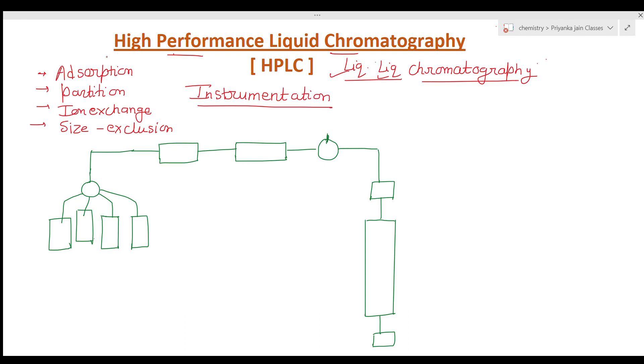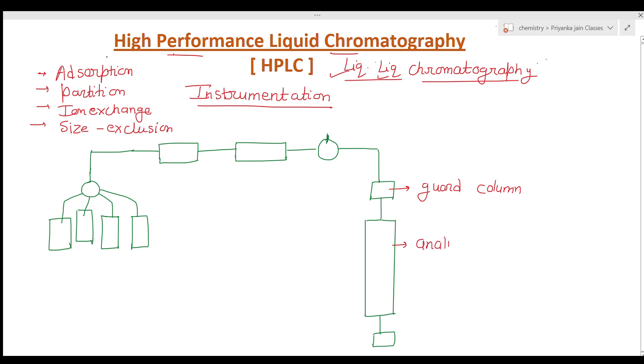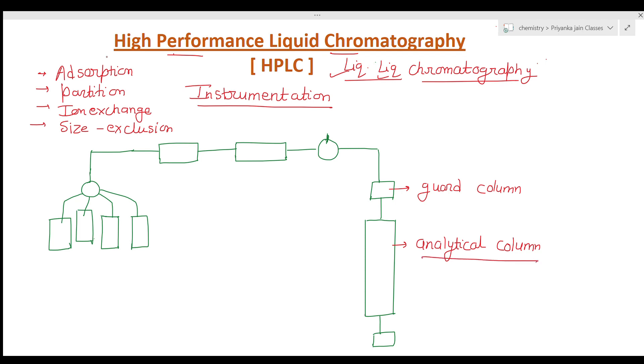In HPLC there are two columns. One column is called the guard column and the other is called the analytical column. In the analytical column, the whole separation performance is carried out — this is the basic chromatographic column where the separation takes place.